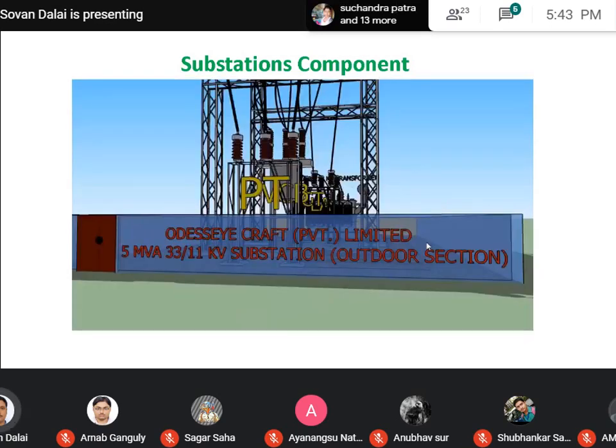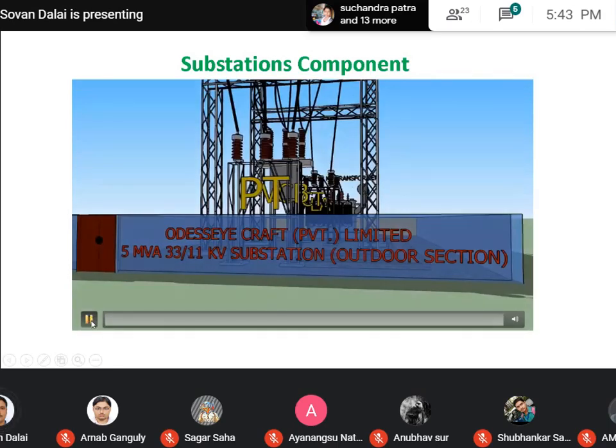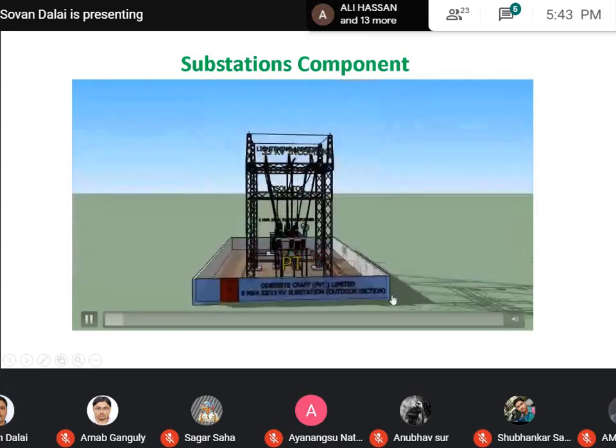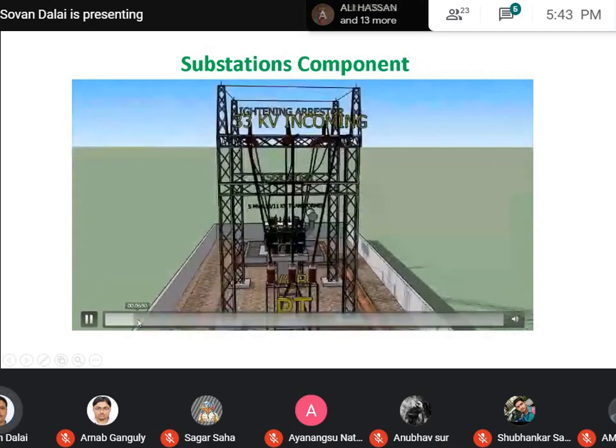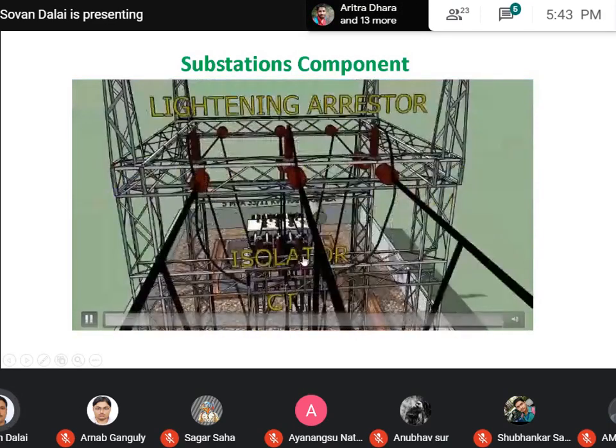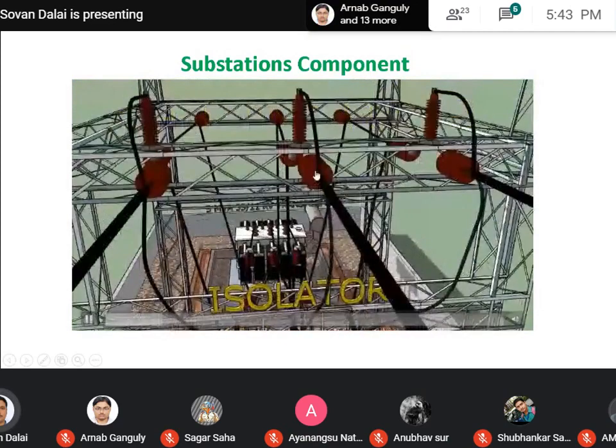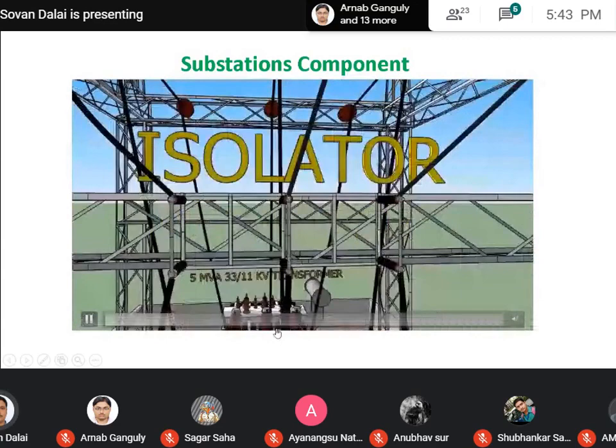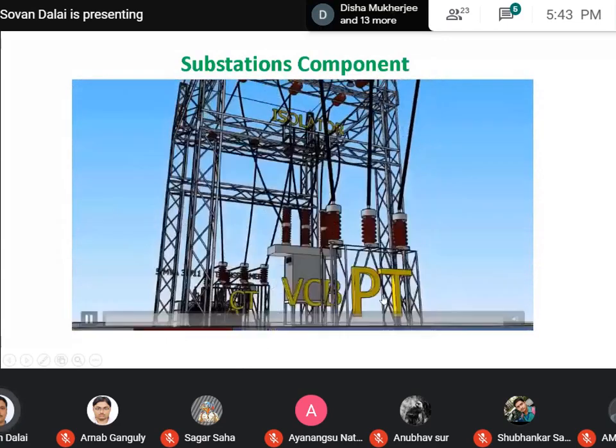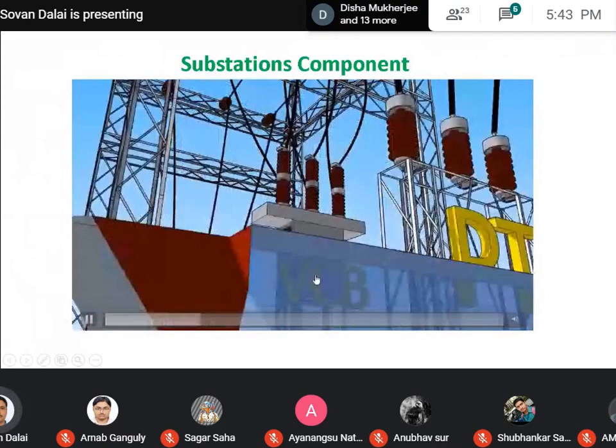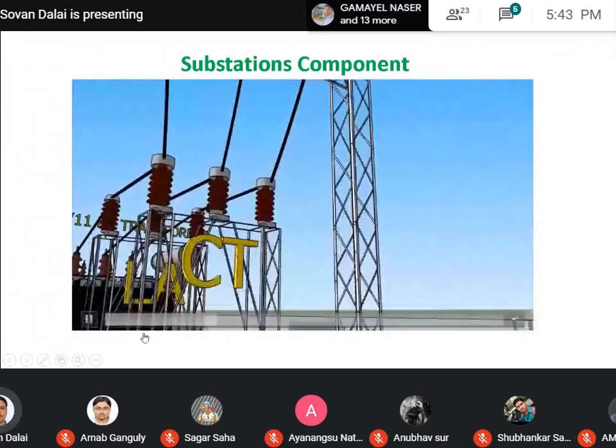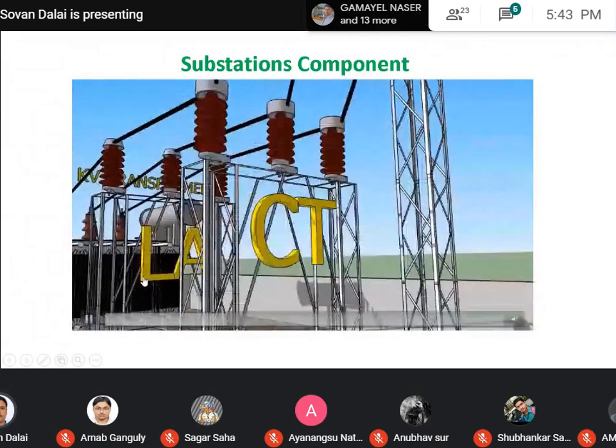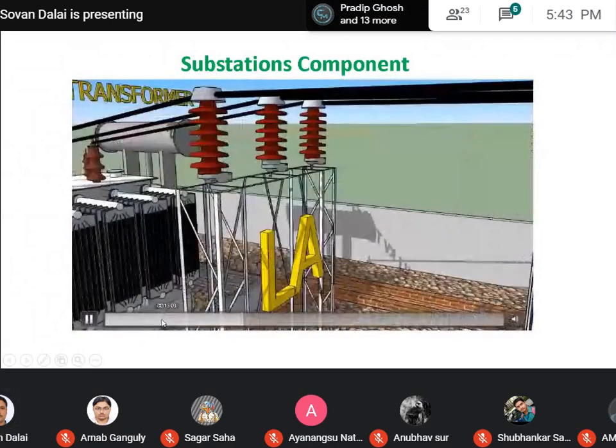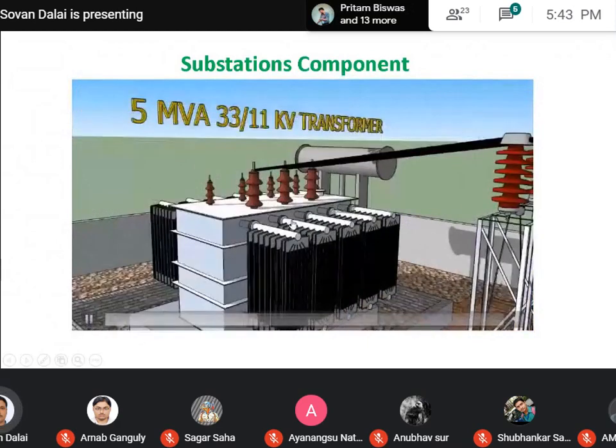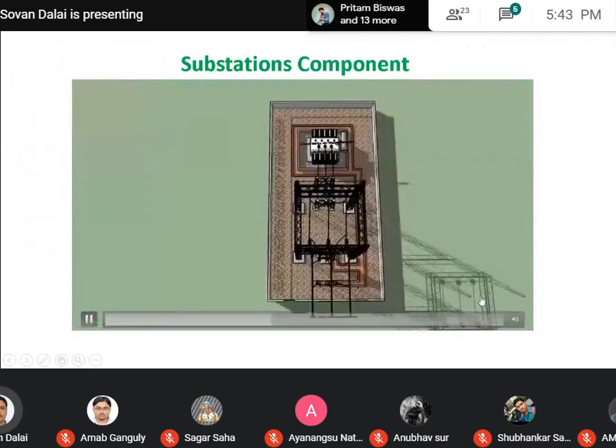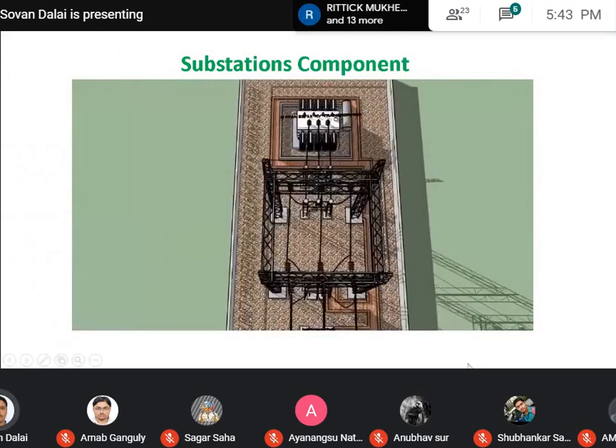So here is just a small video. Just see, this is the substation. These are the different components. This is the 33 kV incoming substation. These are the isolator and the lightning arrestor. This is the major component. And these are, you see, the PT and the vacuum circuit breaker for protection purposes. This is the current transformer for current measuring. And finally, the lightning arrestor is provided to arrest the lightning surge. And this is the main component, the transformer. So these are the different components present inside the substation.